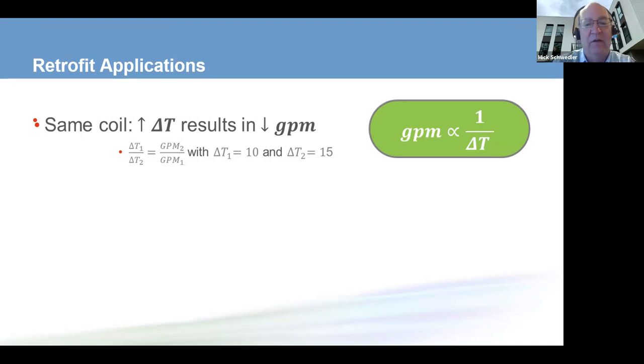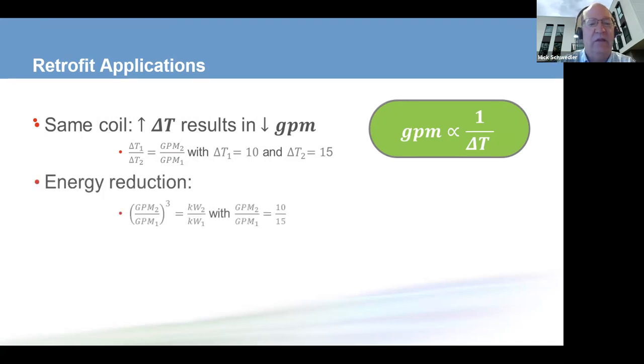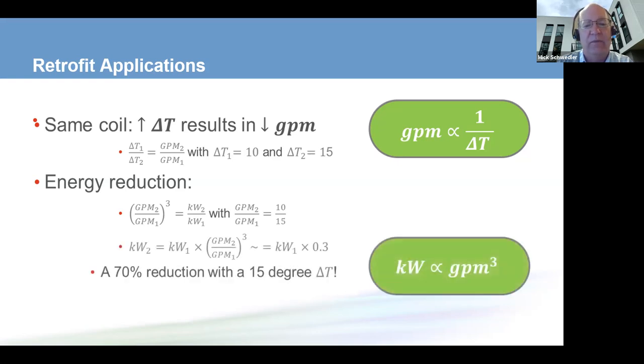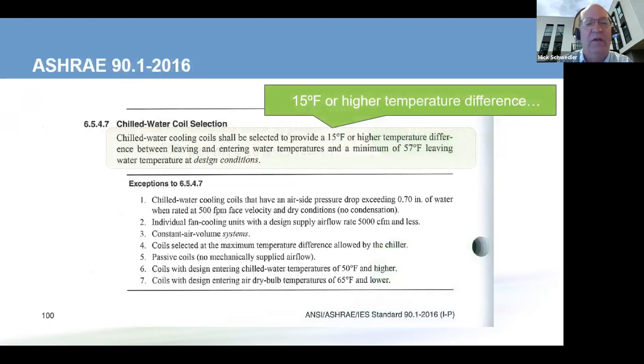They are selected for a particular flow rate and delta T. So if we want to, we can give the coil colder water, reduce the flow rate, and reduce our pumping energy. And that's really the benefit of having a higher delta T and a lower flow rate. The pump power changes with about the cube of the flow rate. So for increasing the delta T, we get a significant reduction in pumping power. And that's the goal with doing this.